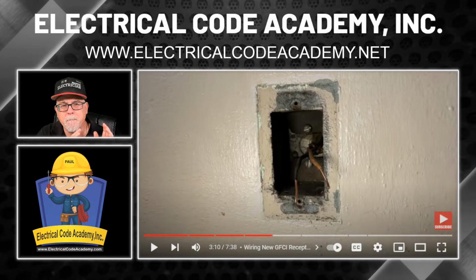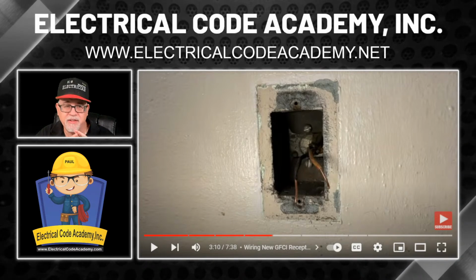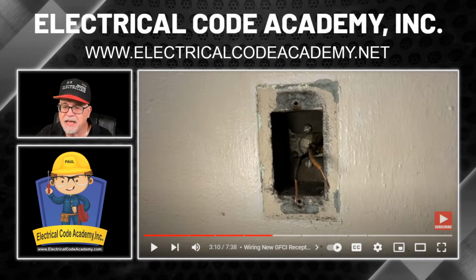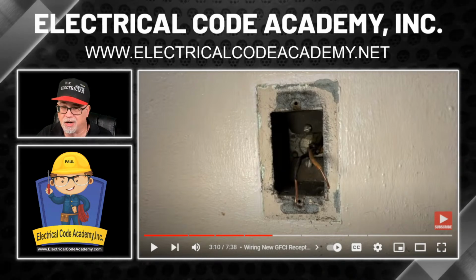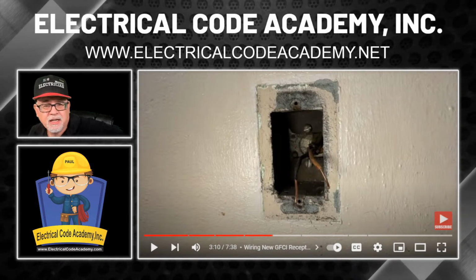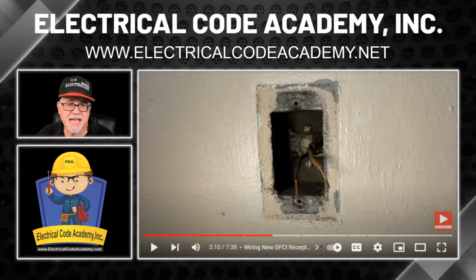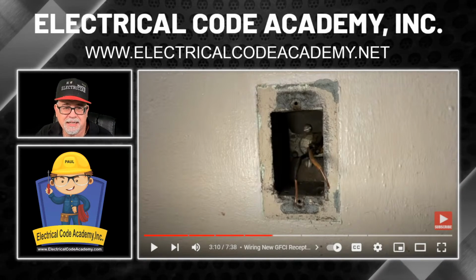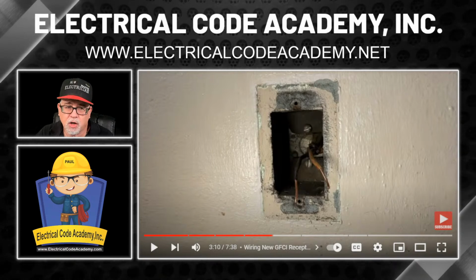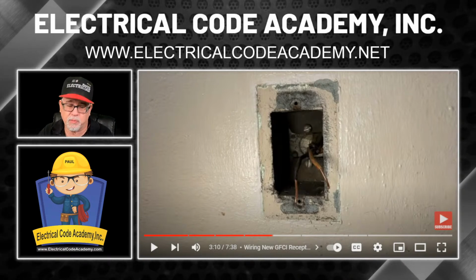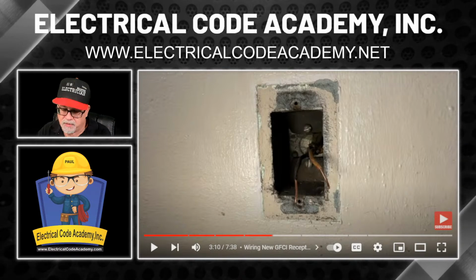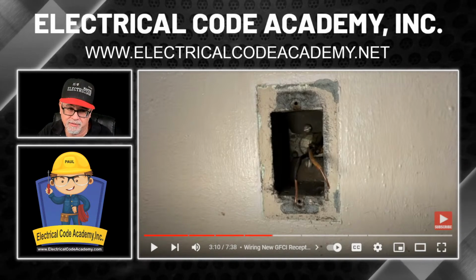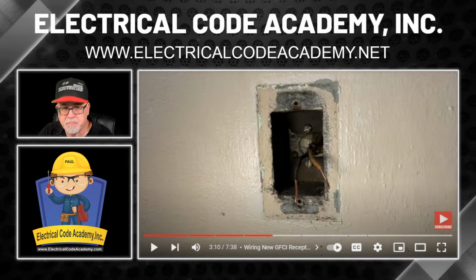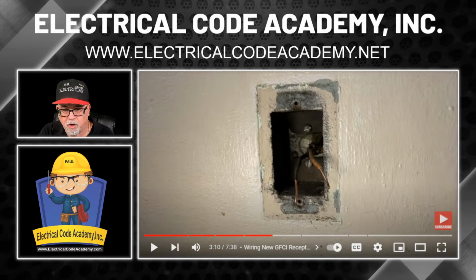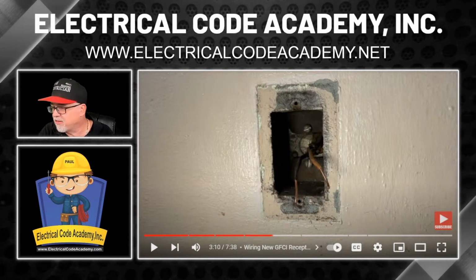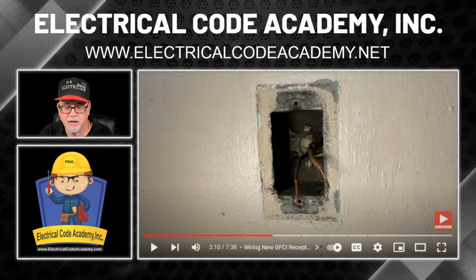Totally different than the old BX style. That was not for use in any of that armor as anything to do with an equipment ground. So again, older homes like this probably have old BX style armor. Just remember, just because it's armor doesn't make it an equipment ground, okay? There is a difference between AC cable and MC cable, and BX is neither. Although it's very common for people to say BX, BX, BX when they're talking about AC or even MC. It is not the same. Okay, want to throw that out there.